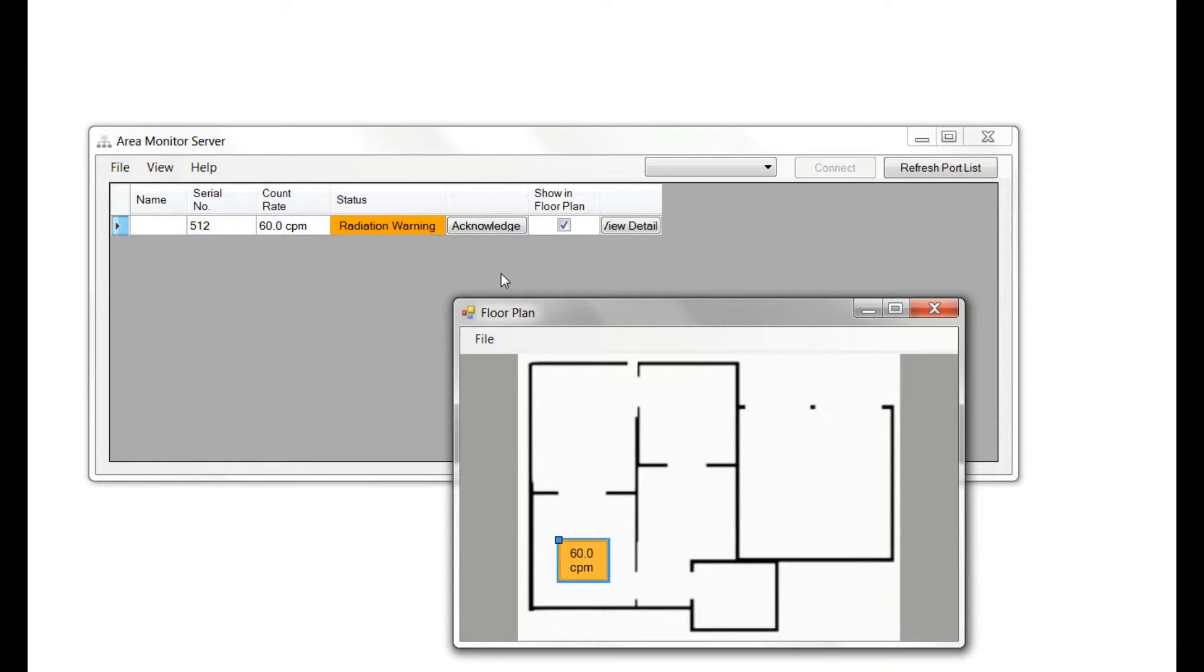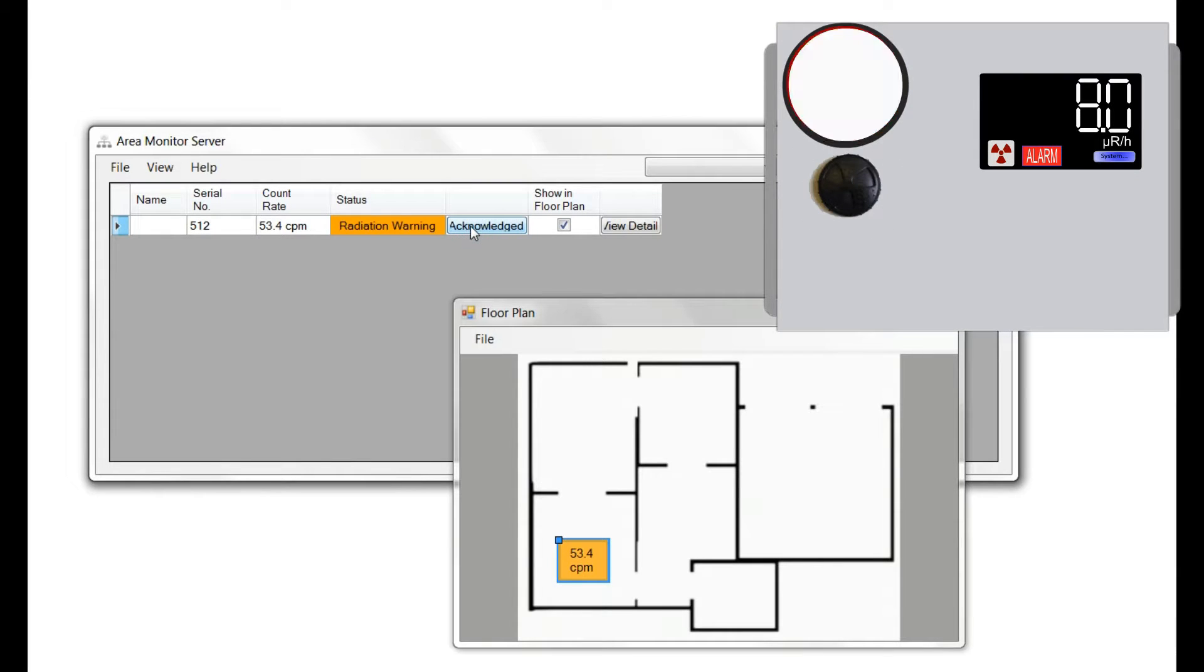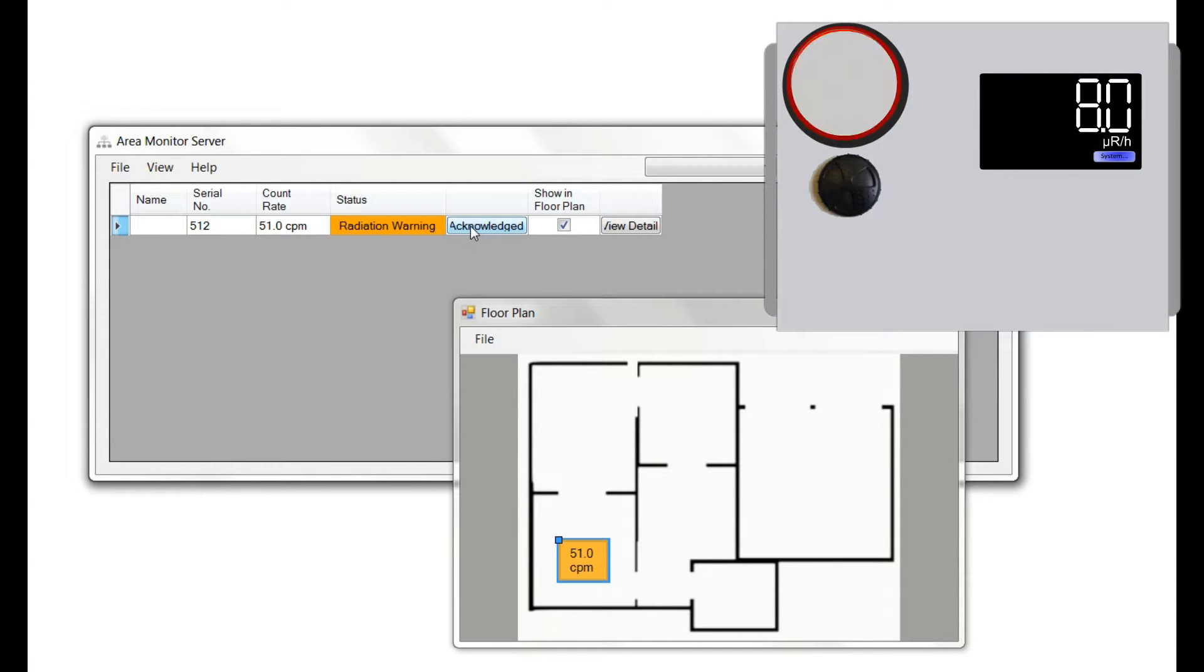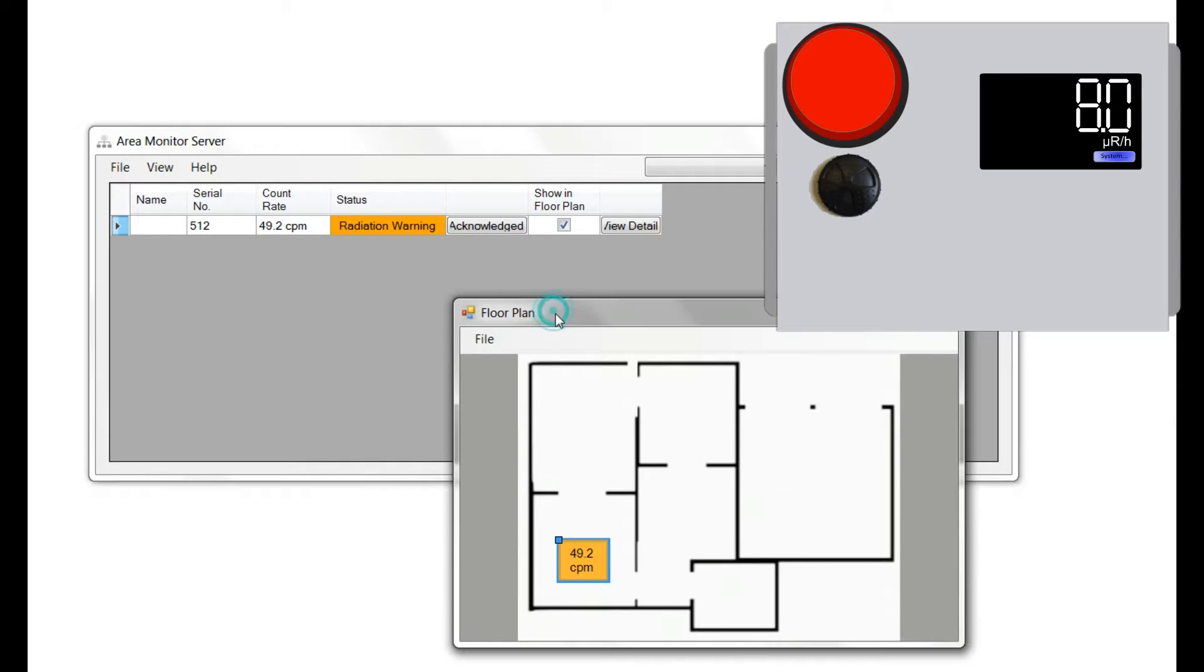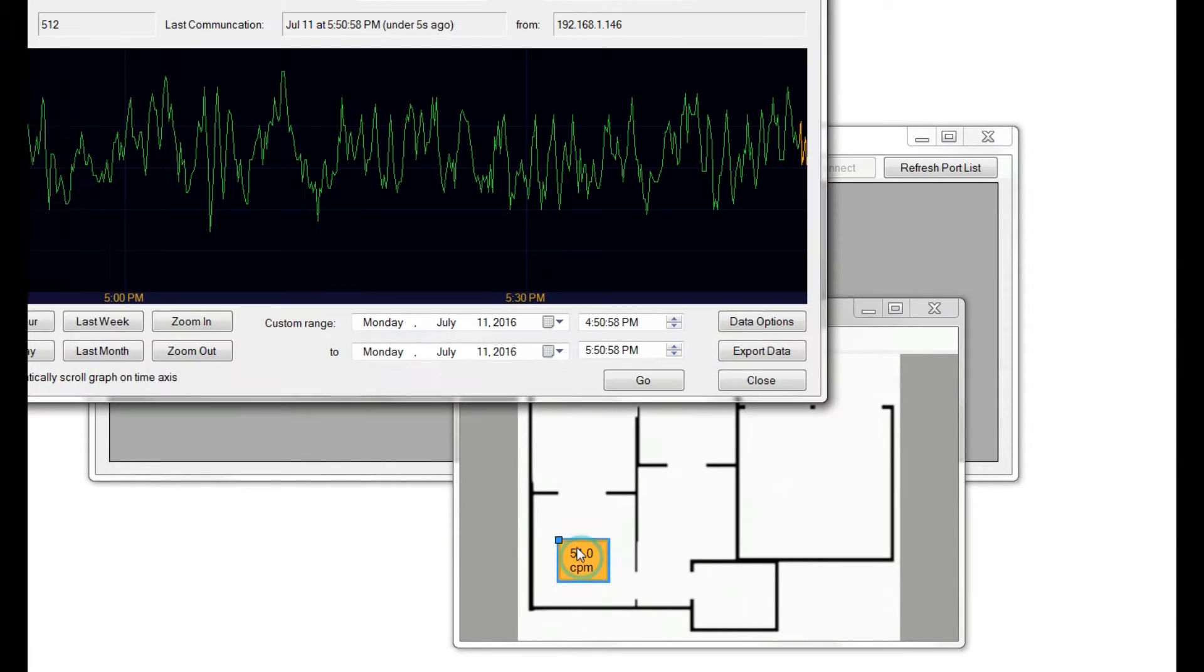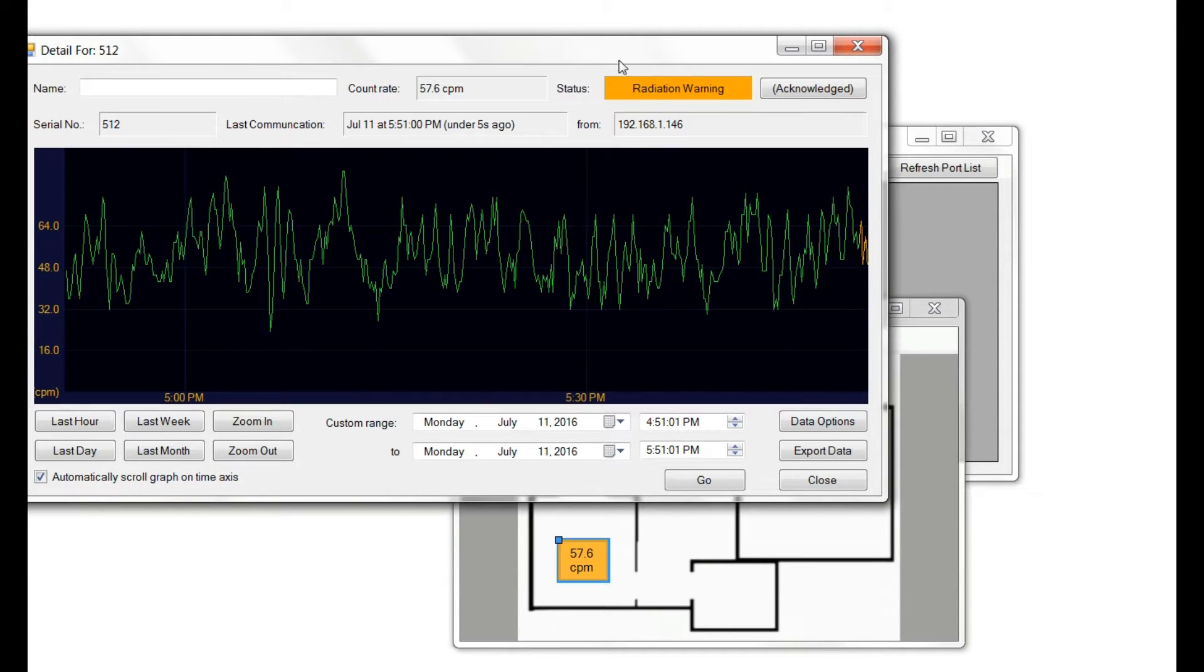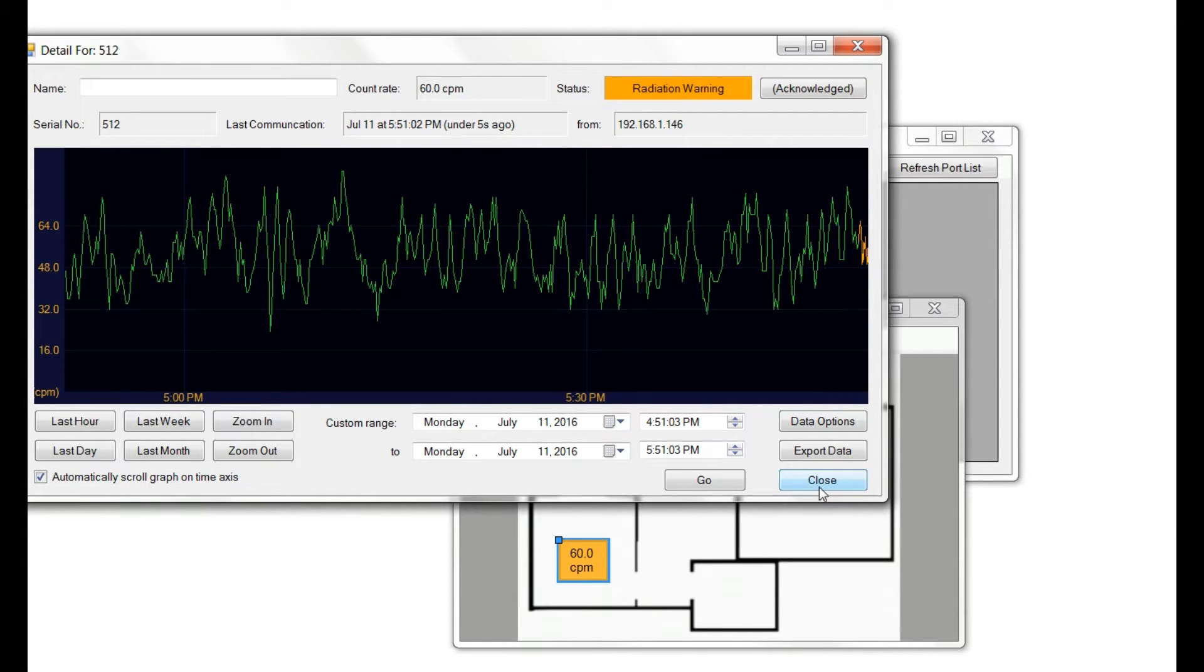To silence the alarm from your software, click Acknowledge. This will silence the alarm at the unit. On the floor plan, the corresponding area monitor icon will show the radiation warning as well.